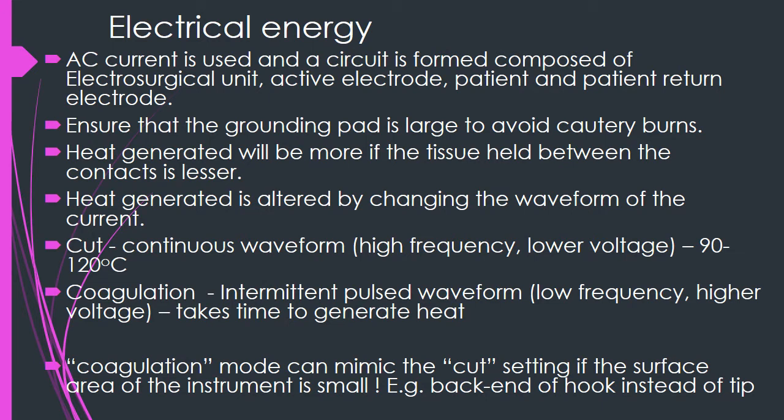Alternating current is used when electrical energy is deployed for hemostasis. The circuit is formed when the electrosurgical unit (ESU) delivers current to the active electrode. The current reaches the patient and returns to the ESU via the indifferent electrode. One should ensure that the grounding pad is very large to avoid cautery burns, because the energy can dissipate over a large surface area. If the tissue held between the two contacts is very large, the heat generated will be less. Therefore, you can alter the heat generated by changing the waveform of the current or the amount of tissue being held.